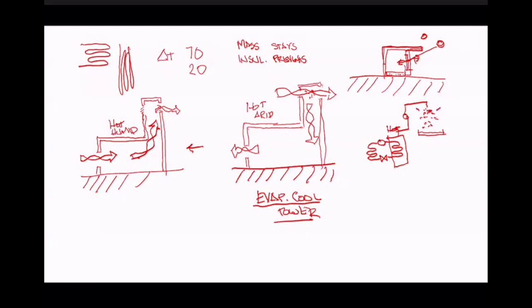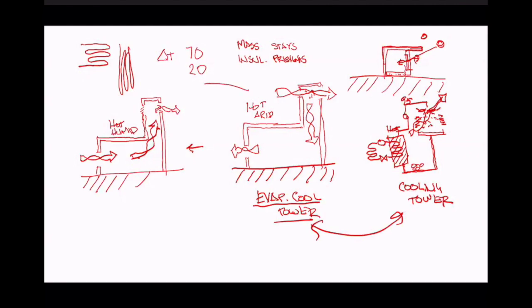We may put a fan there, an impeller fan at the top, and louvers, then bring that water back. So we're always taking water, say at 95 degrees, and allowing air from outside to blow across the water. Some of it evaporates, much of it is cooled, and the evaporating part also helps cool the water, because anytime anything evaporates it makes everything around it cold. We bring that water back at 85 degrees, constantly cooling the hot side of the compression refrigeration loop. This is called a cooling tower. So these are very different, even though two of them have similar names and two look similar when drawn like this.